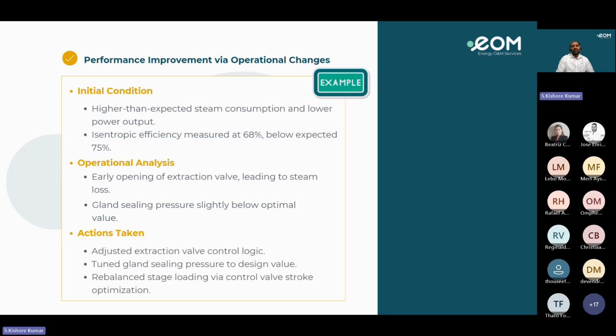So adjust the extraction valve control logic, tune the gland sealing steam pressure to the design value, and rebalance stage loading via control valve stroke optimization. That improved the isentropic efficiency from 68% to 74%. Steam consumption was reduced by approximately 6%, with stable power output, lower vibration and lower exhaust temperature.